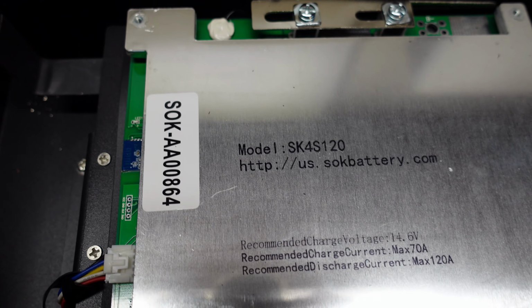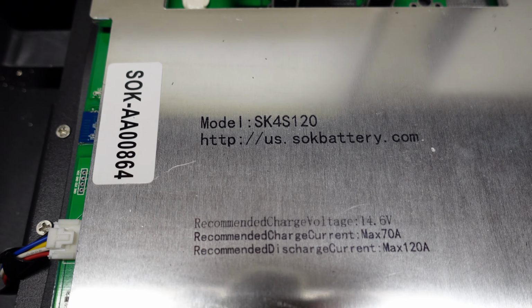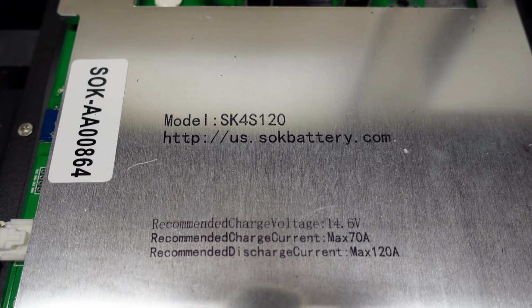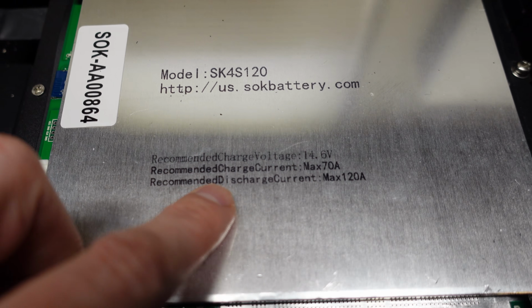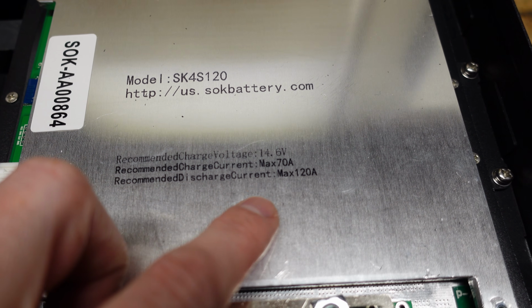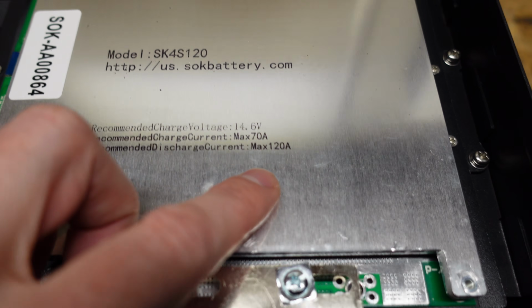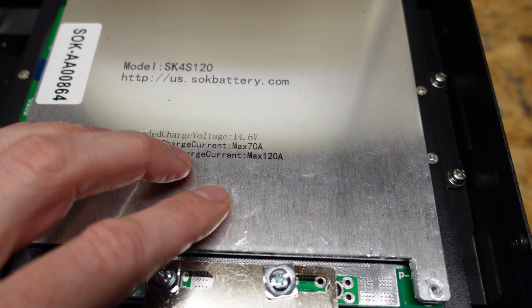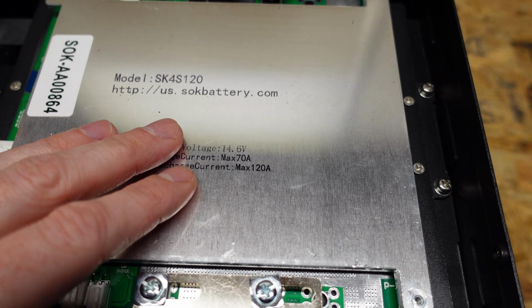Taking a look at our BMS on the top here, there's the model number. It is the SK4S120, and we can see the max charge current is 70 amps and the max discharge current is 120 amps. So we do have 20 amps of headroom both on the charge and the discharge side.